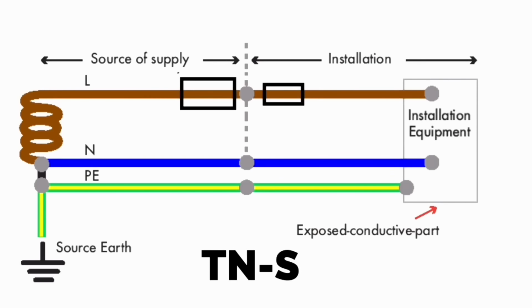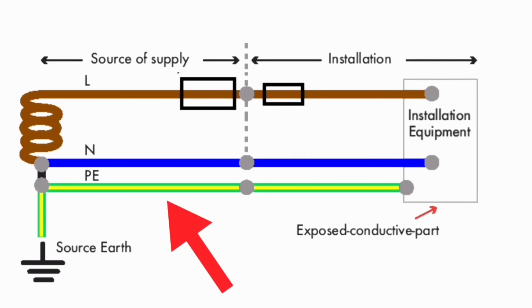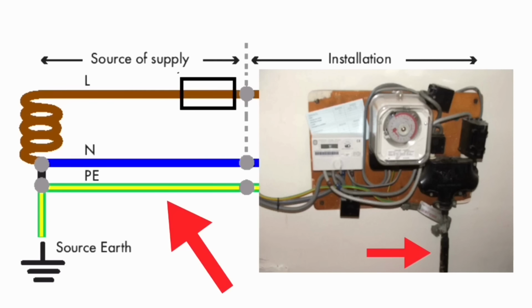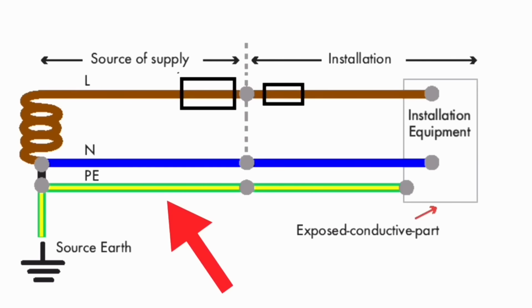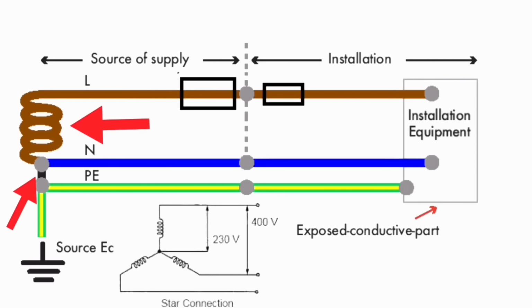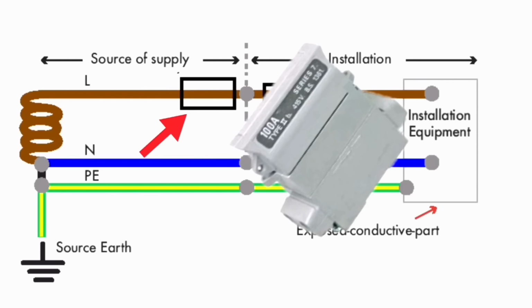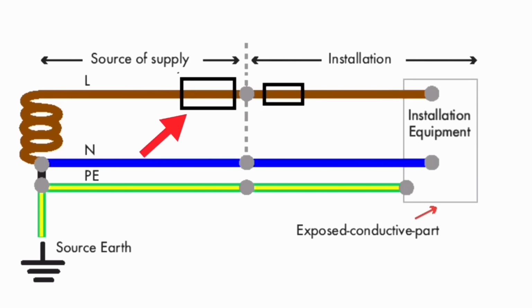The left-hand side of this drawing shows the supply authority's cable with a separate line conductor, a separate neutral conductor, and a separate protective earth conductor coming into our installation. This is the cable we can physically see in the bottom of the cutout. This cable often comes to installations underground, but can also come overhead. This drawing also only shows one of the 3 star connected windings on the supply authority's side, as well as the centre tap point to earth. The supply authorities will provide the metering equipment and the cutout fuse sized 100, 80 or 60 amps for a single phase installation. The supply authority's protective earth will be either lead or steel.